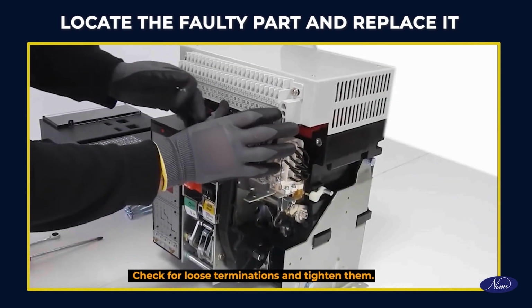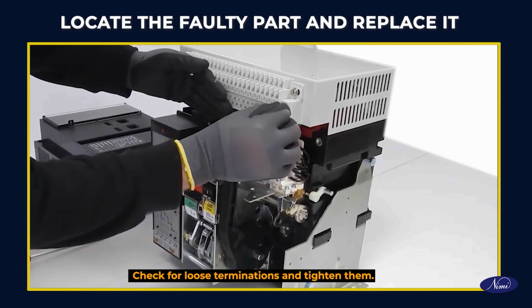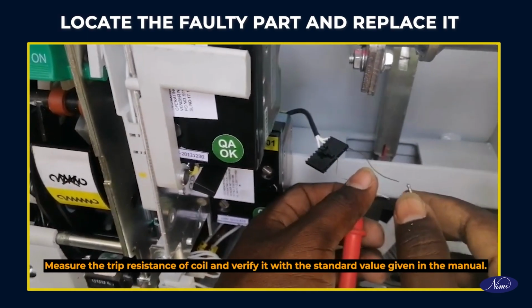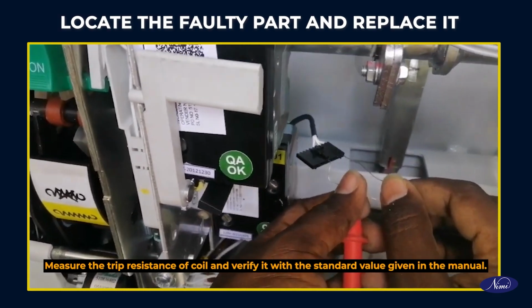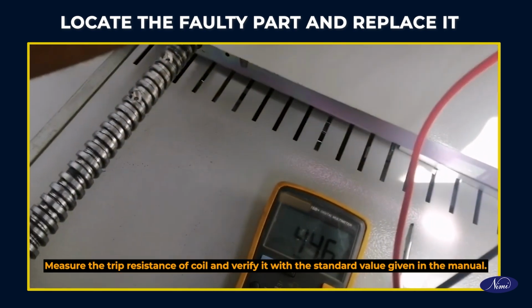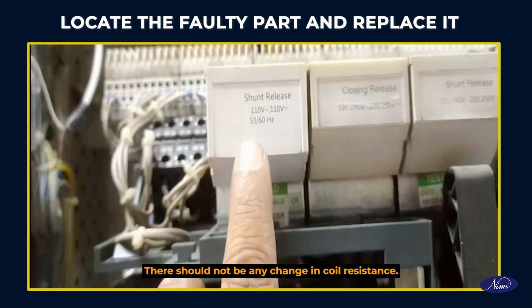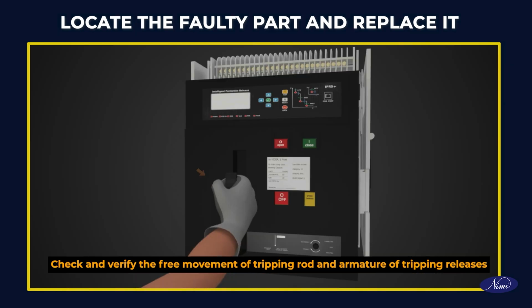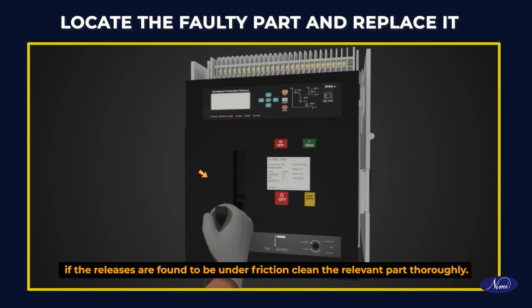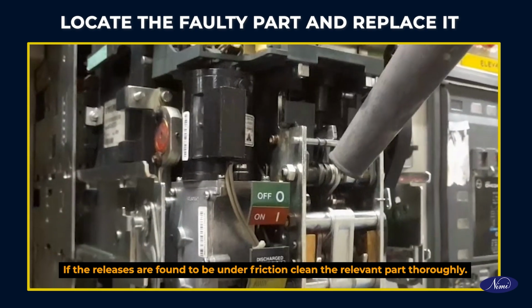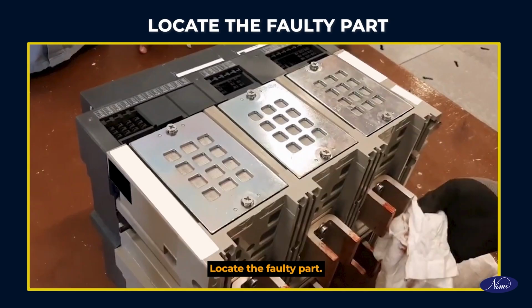Check for loose terminations and tighten them. Measure the trip coil resistance and verify it with the standard value given in the manual. There should not be any change in coil resistance. Check and verify the free movement of tripping rod and armature of tripping releases. If the releases are found to be under friction, clean the relevant part thoroughly. Locate the faulty part.